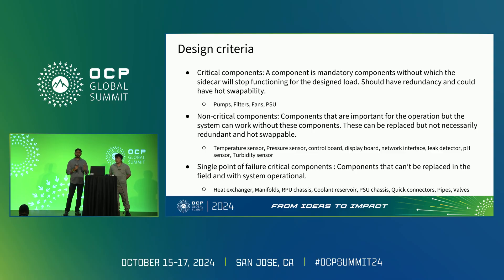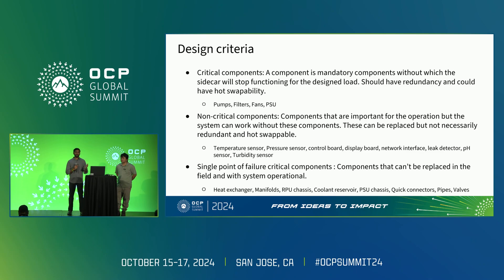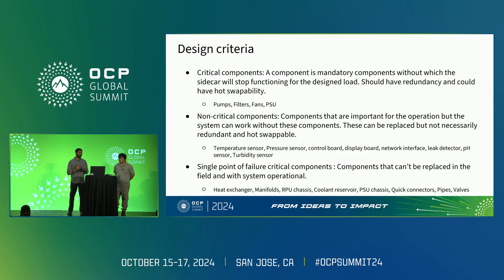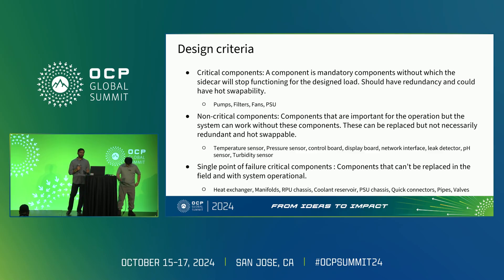Non-critical components are defined as components that need to be present but do not necessarily require hot-swapping — for example, a thermocouple or pressure sensor. Without them, the control system can automatically default to maximum cooling capacity and still operate, though not very efficiently. These need to be replaced in a timely fashion for efficiency, but they will not stop the sidecar from operating.